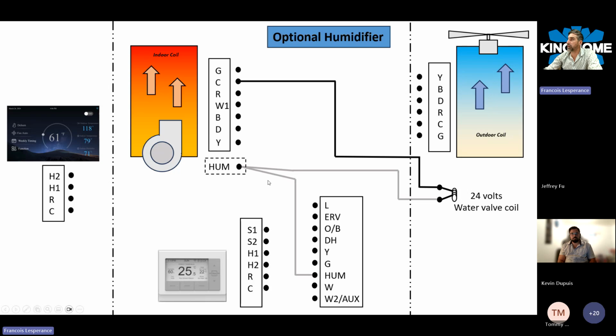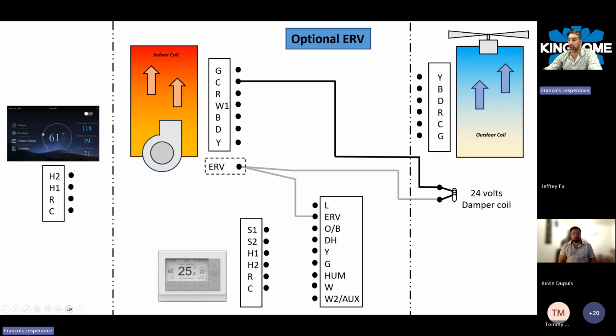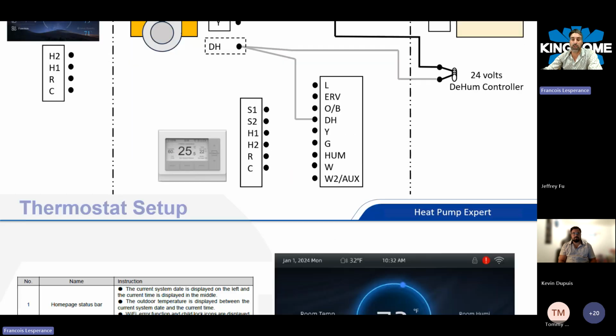If you have some more optional equipment like a humidifier, ERV, or a dehumidifier, you can use those three different outputs, ERV, DH, or HUM, to power it up with 24 volts, like a coil or a relay. At that point, it's up to you to connect your options there.